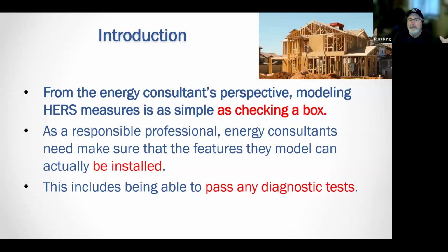That's fine, but what if it's an indoor air quality system attached to the return side of the grill? Where is that outlet—where is that intake on the outside of the house bringing in that air? If it's 25 feet up in the air underneath an eave, the HERS rater is probably not going to be able to test that. It's going to be very, very difficult to test.